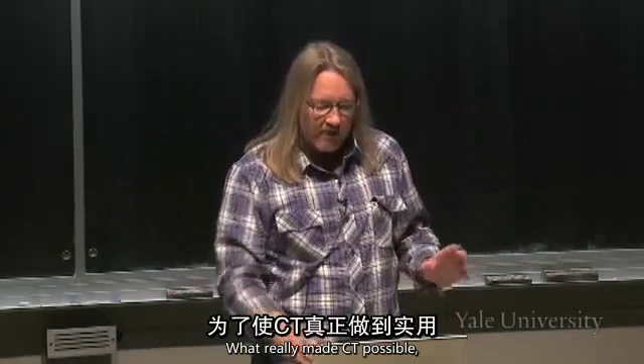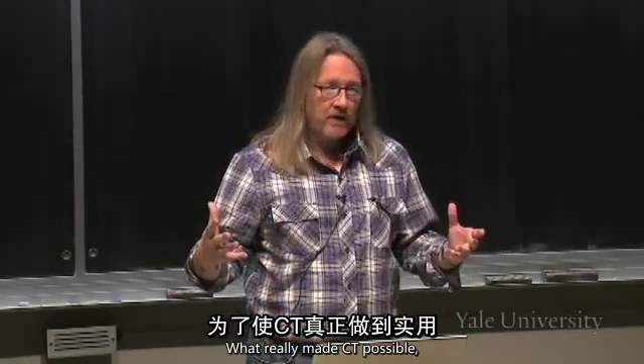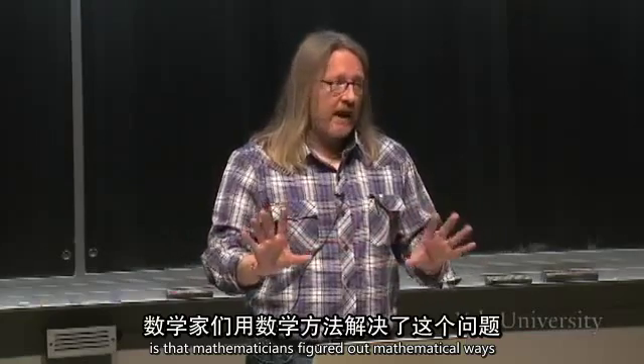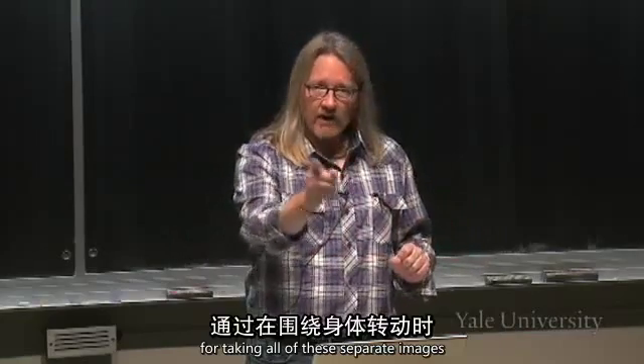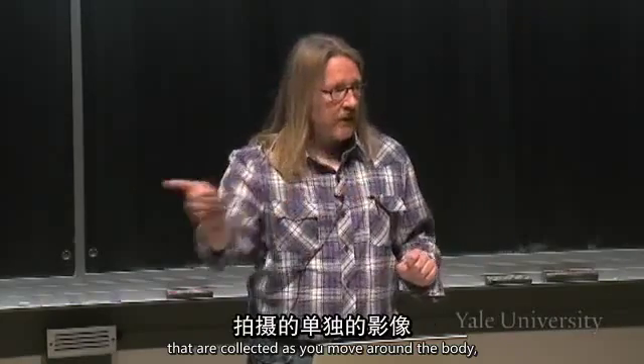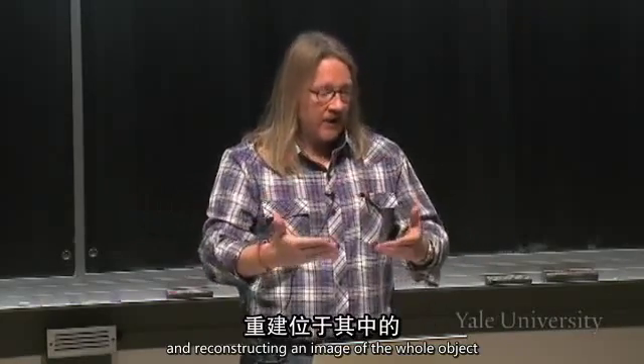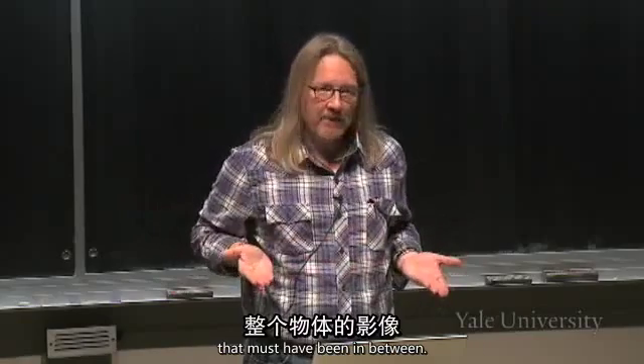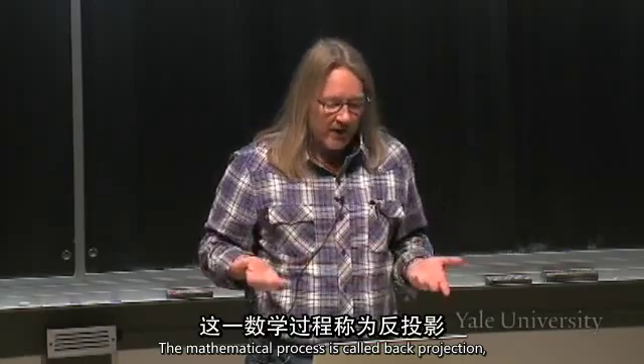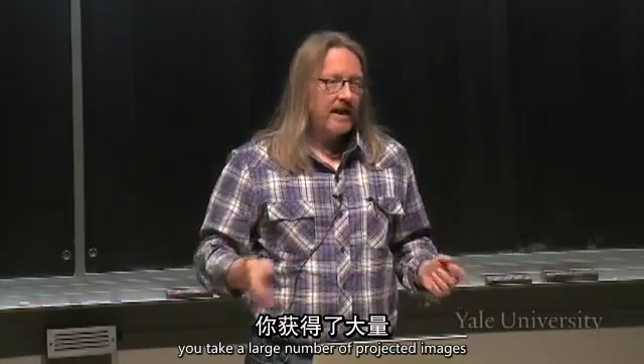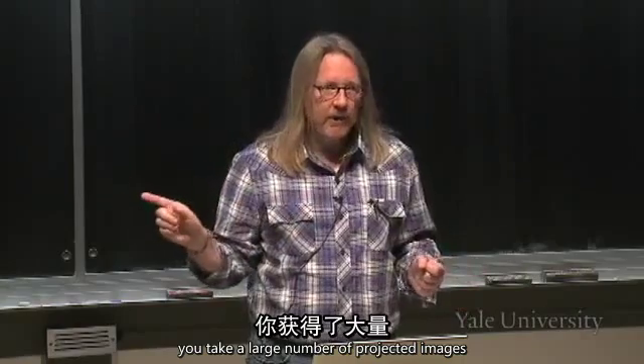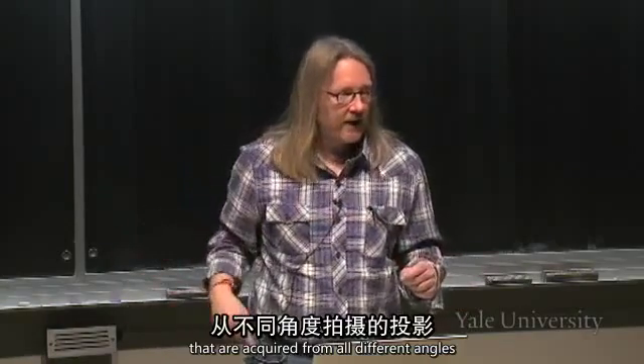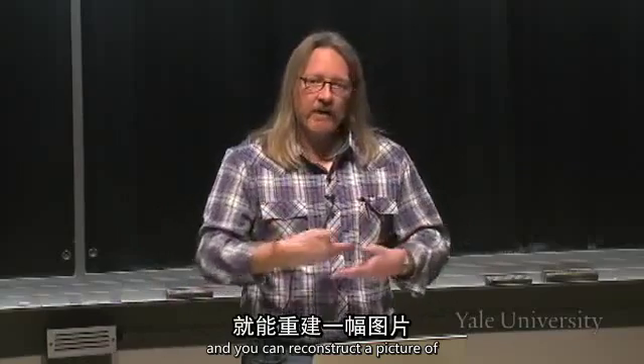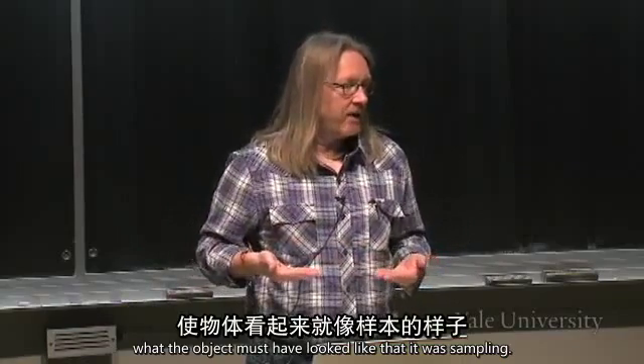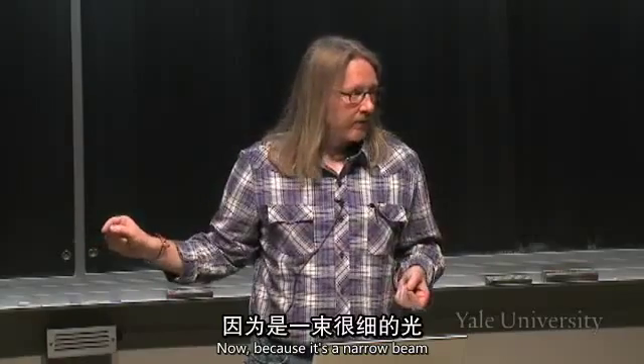And so what really made CT possible is that mathematicians figured out mathematical ways for taking all of these separate images that are collected as you move around the body and reconstructing an image of the whole object that must have been in between. Right? The mathematical process is called back projection. You take a large number of projected images that are acquired from all different angles, and you can reconstruct a picture of what the object must have looked like that it was sampling.